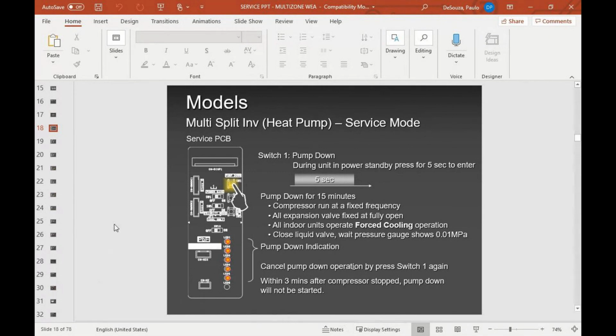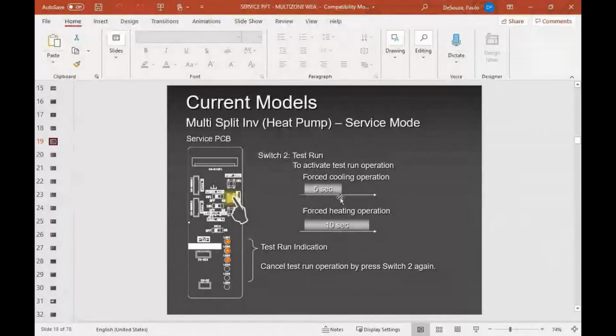So that little board over there is what I'm going to explain in the next few slides. Okay, guys? There is this button here that is called the pump down button, switch 1, SW1. So you can pump down the system with no issues. If you have a problem, maybe you want to add an indoor unit, pump down from the outdoor unit, close the liquid line, press that switch for 5 seconds, your pump down will start.